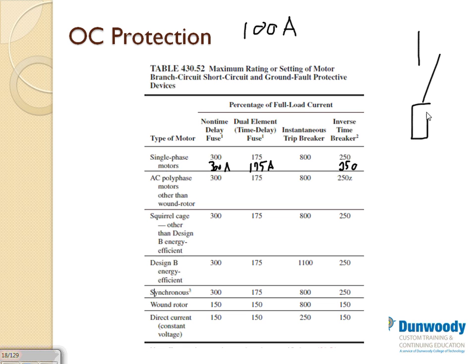So here's my fuse, and here's my motor. There you're going to have an overload. I'm just showing a few of these. So you have your motor right there. That fuse is going to be 300 amp or 175 amp, or if it's a circuit breaker, 250. See the difference between the types? Has anybody ever used an instantaneous trip circuit breaker?